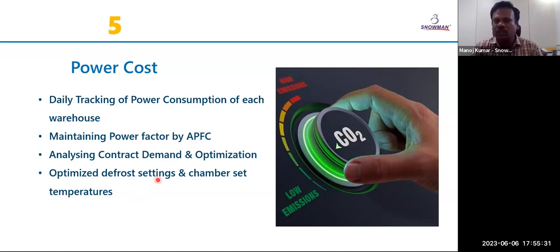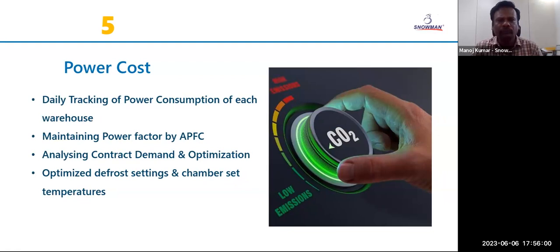Similarly, as I said, we optimize defrost settings based on the chambers, and the chamber set temperature based on requirement, operations and outside climate. Suppose in winter we reduce the defrost; in summer, where operations are very high, we increase the defrost. So that is all very dynamic operational monitoring.